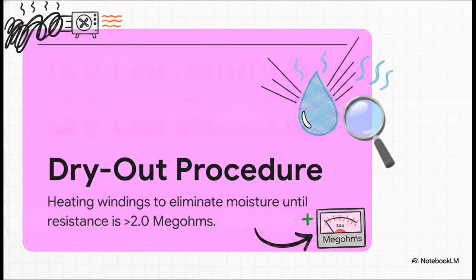On these systems, anything under 2.0 megohms indicates some serious, dangerous moisture or dirt contamination, and it mandates an immediate dry-out procedure. That means you literally have to actively heat the windings, whether that's via built-in space heaters or a forced air oven, to bake that moisture completely out of the insulation. You keep at it until your resistance climbs steadily back up above that 2.0 megohms safety threshold.